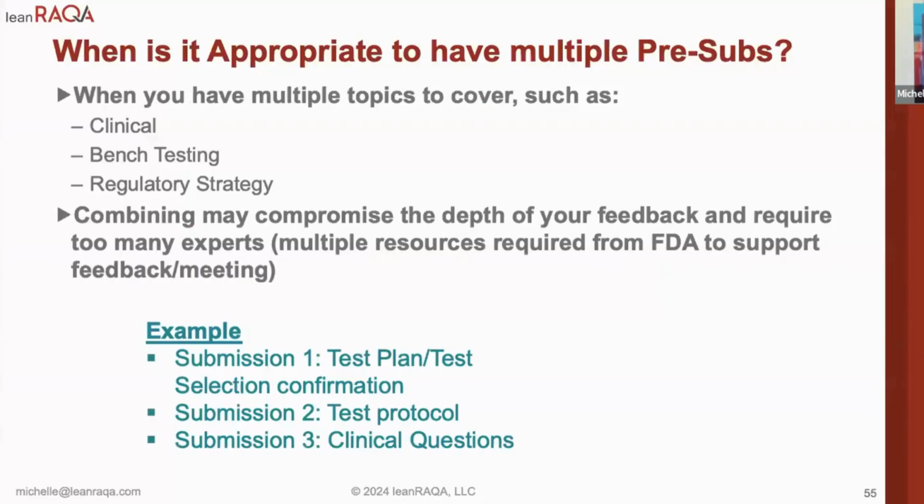So here's some of my lessons learned. When is it appropriate to have multiple PreSubs? Well, when you have multiple really in-depth topics to cover, like clinical, bench, and regulatory strategy. Combining these might compromise the depth or quality of review that you are seeking.